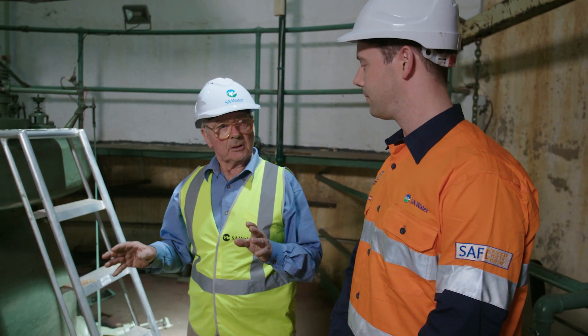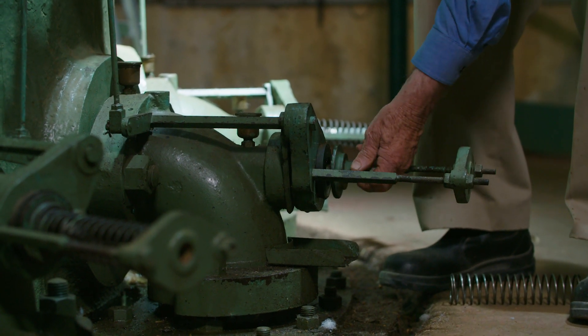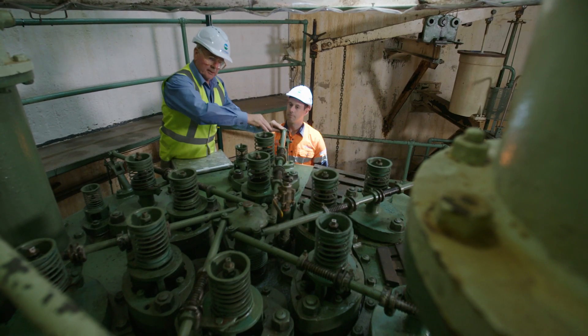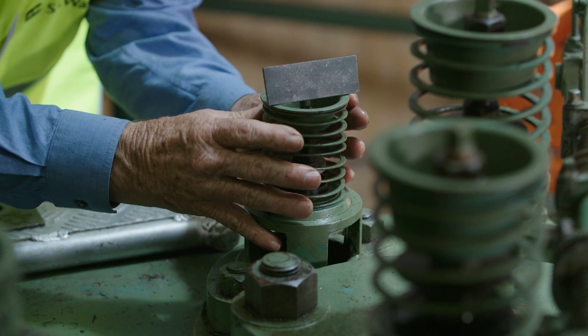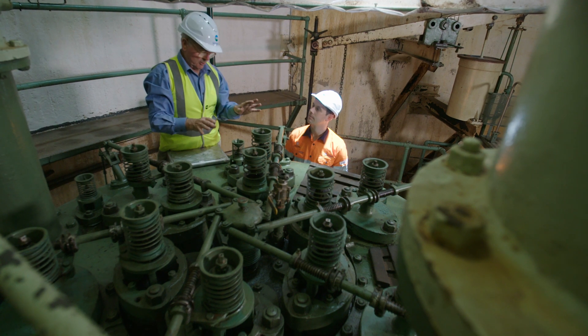All right, we can get the Humphrey pump ready. Lyn, what do we do in regards to preparation work? After we do the outside preparation work, we then need to lubricate the pump. The first thing we lubricate, which often takes the longest, is lubricating the exhaust valves. We lubricate these in sequence so you lubricate all of one, then all of the next — that way you make sure you don't miss anything out. Then once you've lubricated and you've got it quite free, you get this two-ounce weight, sit it on top. Hear that clunk? That's ideal — that's calibrated. These valves will open up; they're all spring-loaded so they're always closed. The only way they can open is if a partial vacuum is created inside and they're sucking. Right, that's all your valves now lubricated — we're ready to go from this point of view.